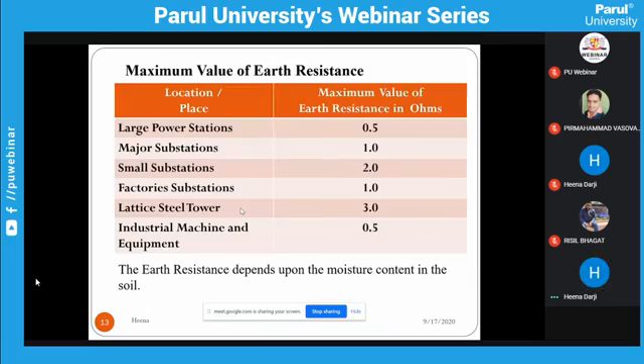Okay. Now, the maximum value of earth resistance. There are different earth resistances in different parts and different human bodies. So this depends on location and place. Now, large power systems, substations of about 220 kV, meaning 220 kV, 132 kV, 400 kV. In these power systems, our earth resistance is 0.5 ohm. Now, normal substations mean 110 kV, 132 kV. In all these substations, we use one earth resistance.